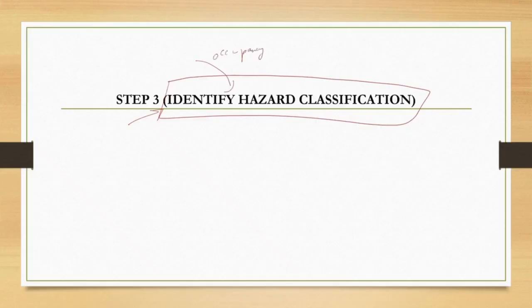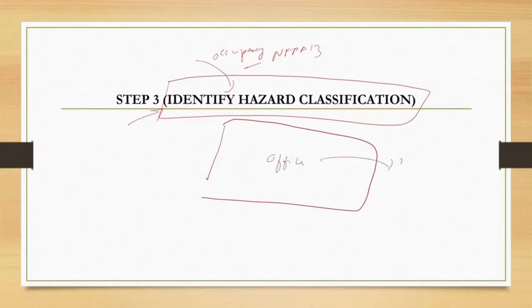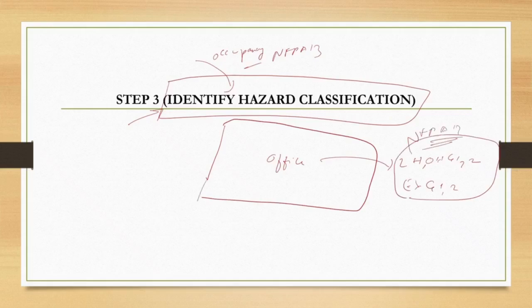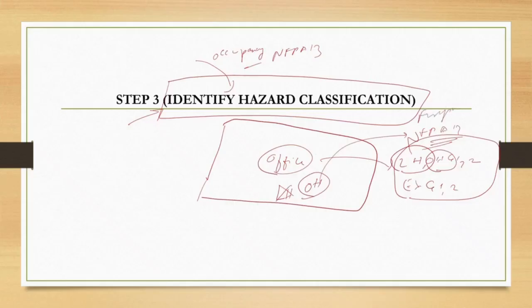Once we confirm sprinklers are required, we need to identify the occupancy hazard classification as per NFPA 13 — whether the building comes under light hazard, ordinary hazard group 1 or 2, or extra hazard group 1 or 2. If we select the wrong hazard classification — for example, our office comes under light hazard but we selected ordinary hazard — it will impact the fire pump capacity, pipe sizing, and affect the entire system.